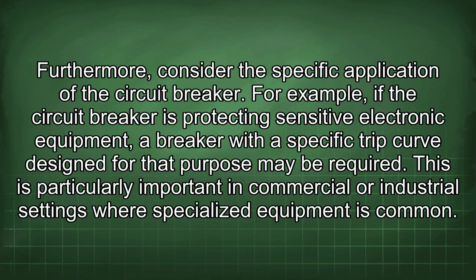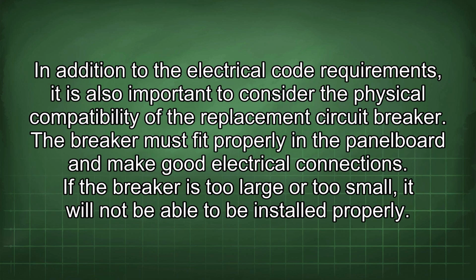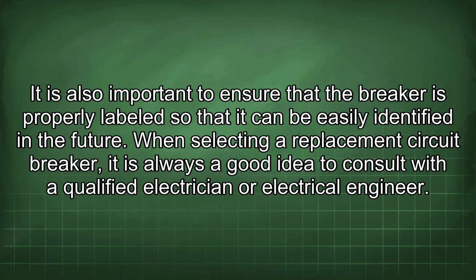Furthermore, consider the specific application of the circuit breaker. For example, if the circuit breaker is protecting sensitive electronic equipment, a breaker with a specific trip curve designed for that purpose may be required. This is particularly important in commercial or industrial settings where specialized equipment is common. In addition to the electrical code requirements, it is also important to consider the physical compatibility of the replacement circuit breaker. The breaker must fit properly in the panel board and make good electrical connections. If the breaker is too large or too small, it will not be able to be installed properly. It is also important to ensure that the breaker is properly labeled so that it can be easily identified in the future.